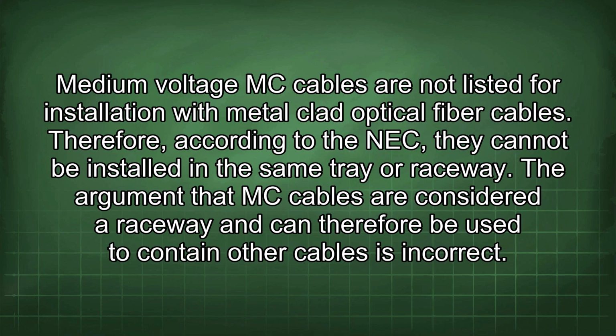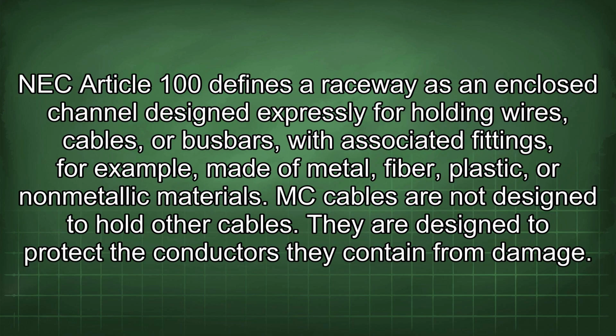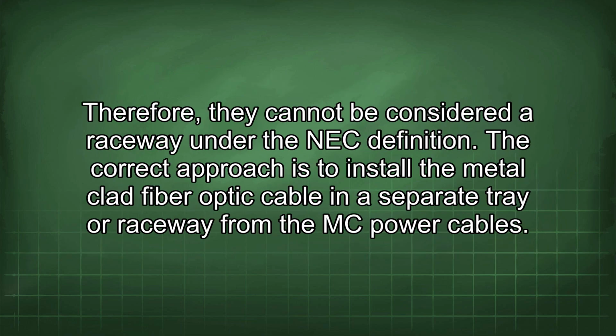The argument that MC cables are considered a raceway and can therefore be used to contain other cables is incorrect. NEC Article 100 defines a raceway as an enclosed channel designed expressly for holding wires, cables, or busbars, with associated fittings, for example, made of metal, fiber, plastic, or non-metallic materials. MC cables are not designed to hold other cables. They are designed to protect the conductors they contain from damage. Therefore, they cannot be considered a raceway under the NEC definition.